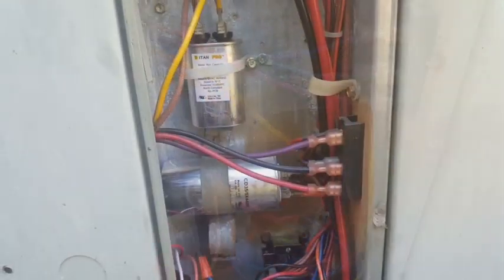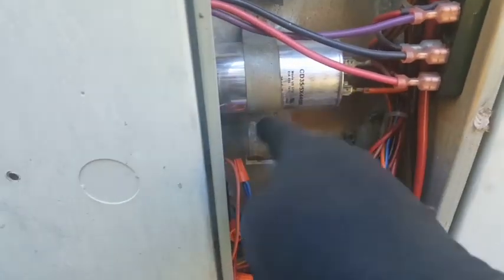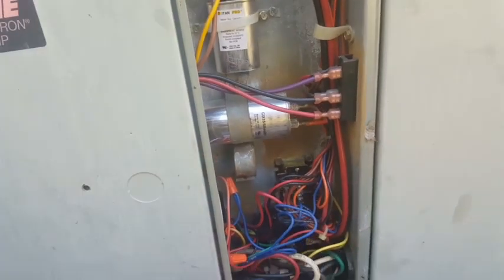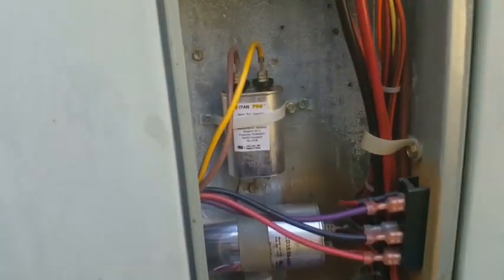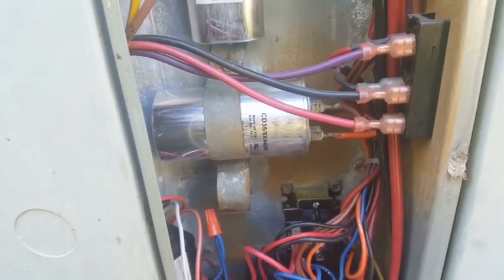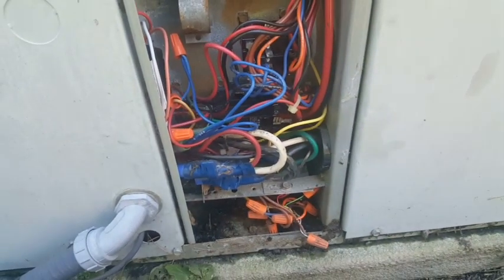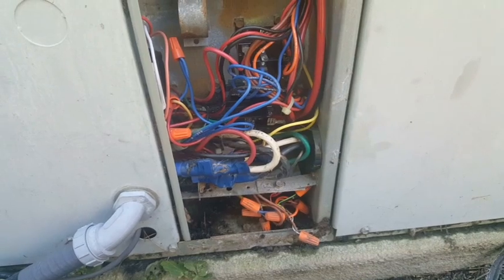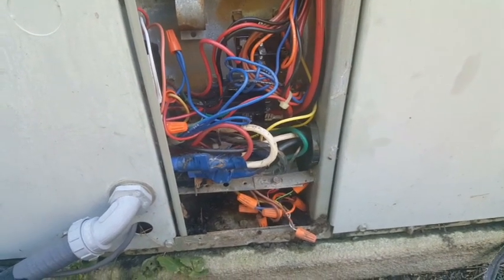We have our capacitor strapped up now. We didn't actually use this little strap at the bottom. It's still hooked onto the other strap, so it's going to stay there. Our blower capacitor, dual run for the compressor and fan motor, so we should be done in here. I'll take a peek in the crawl space. Ew. And then we'll start her up.